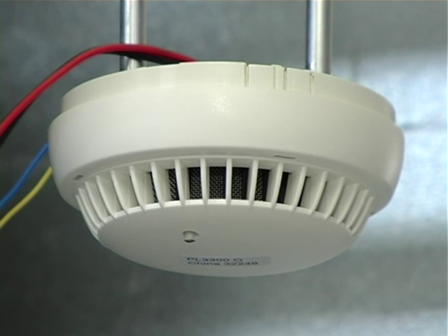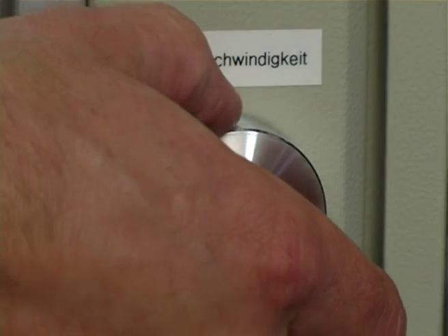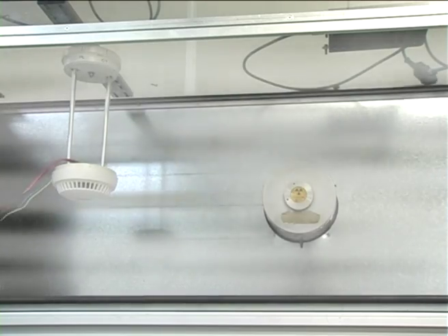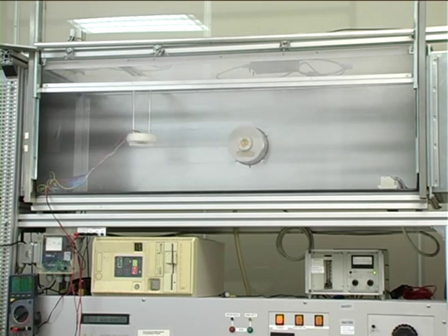This optical detector furthermore includes special electronic settings in order to guarantee the fail-safe use in rooms and shafts with wind speed air currents of up to 20 meters per second. Under these extreme conditions, standard detectors are not able to detect in a reliable way and tend to false alarms.